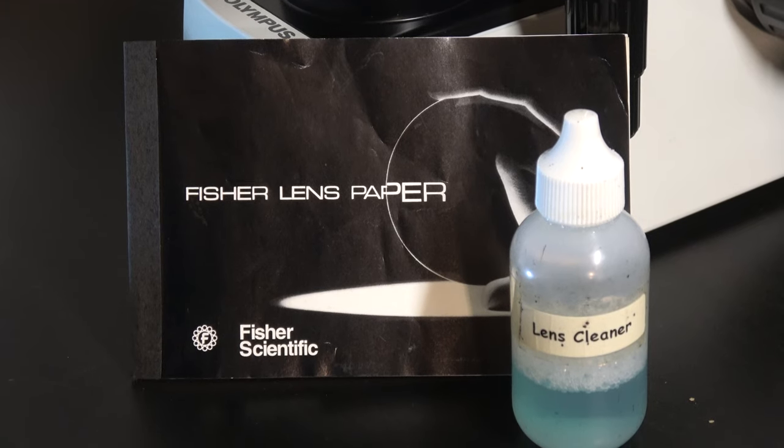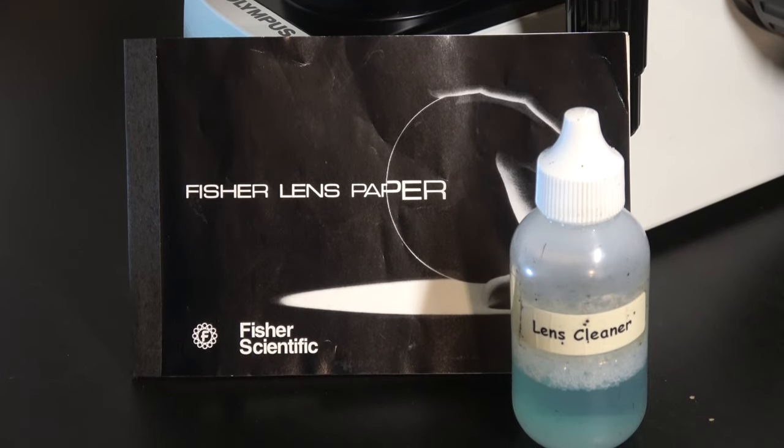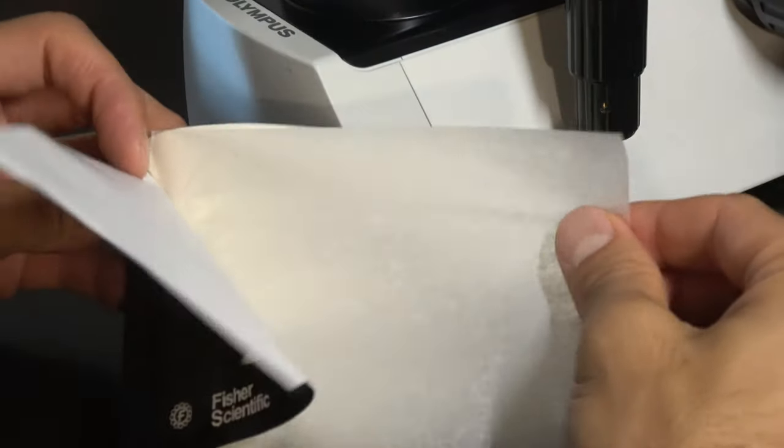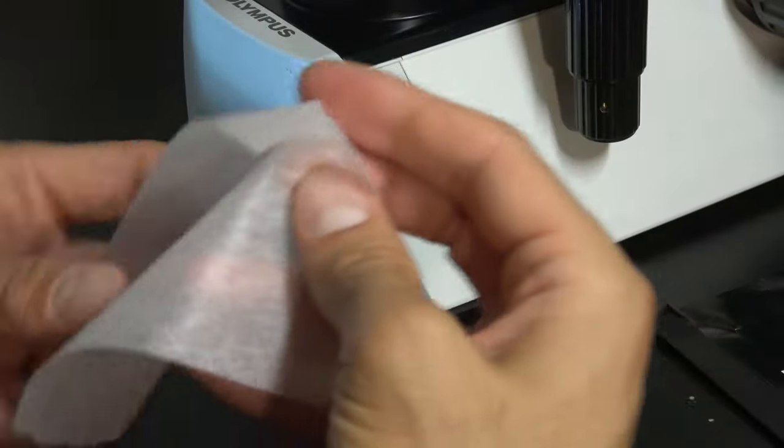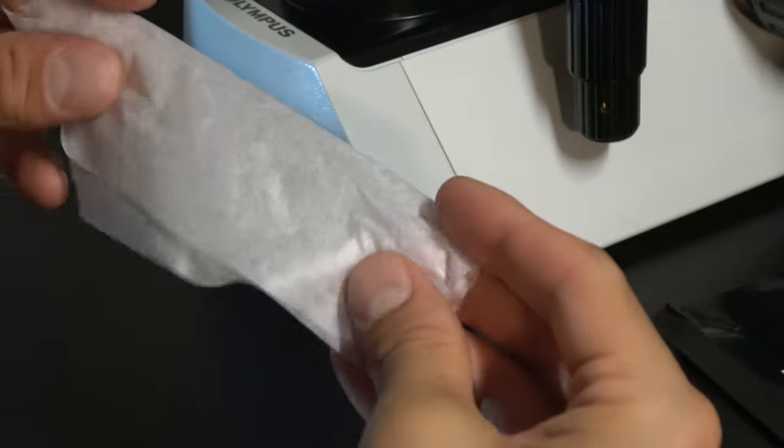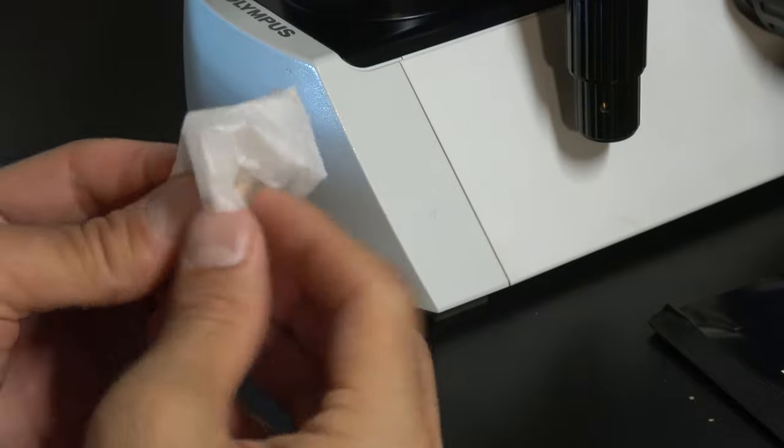For the objectives, it is imperative that you use lens paper only. Paper towels and chem wipes can scratch the lenses. Pull a leaf of lens paper out and avoid getting oils from your hands on the region where you will clean the lens with.